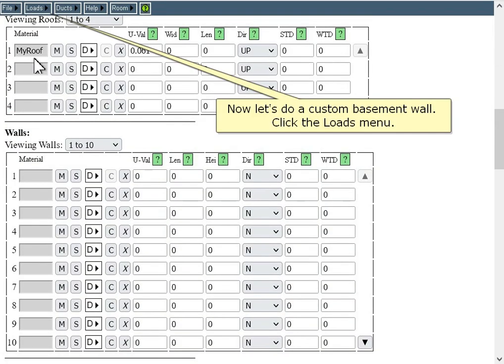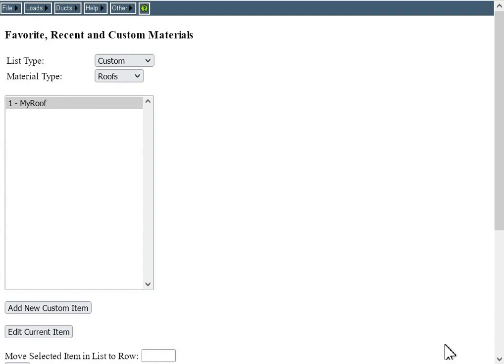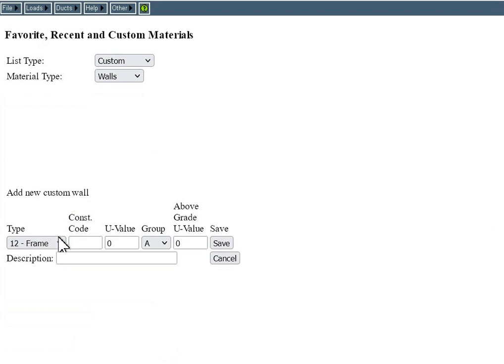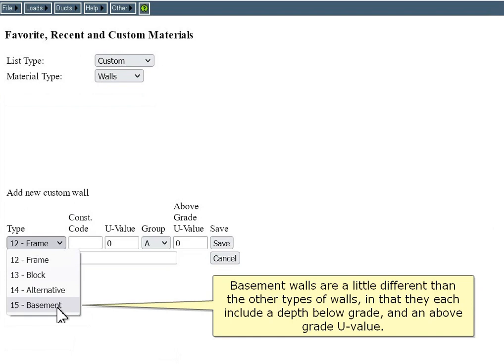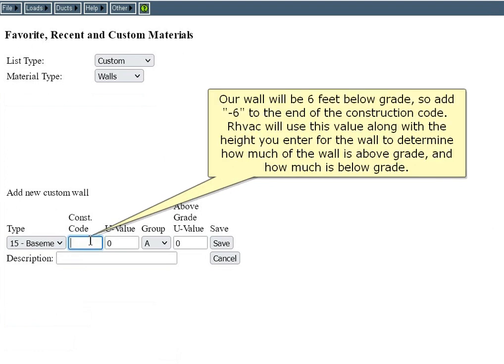Now let's do a custom basement wall. Click the Loads menu, then click Edit Favorites Recent Custom Materials. Select Walls for the material type, then click Add New Custom Item. Select 15 Basement Wall for the type. Basement walls are a little different in that they each include a depth below grade and an above-grade U-value. For a basement wall, the construction code must end with a dash followed by the number of feet below grade of the bottom of the wall. Our wall will be 6 feet below grade, so add dash 6 to the end of the construction code. RHVAC will use this value along with the height you enter for the wall to determine how much is above grade and how much is below grade.